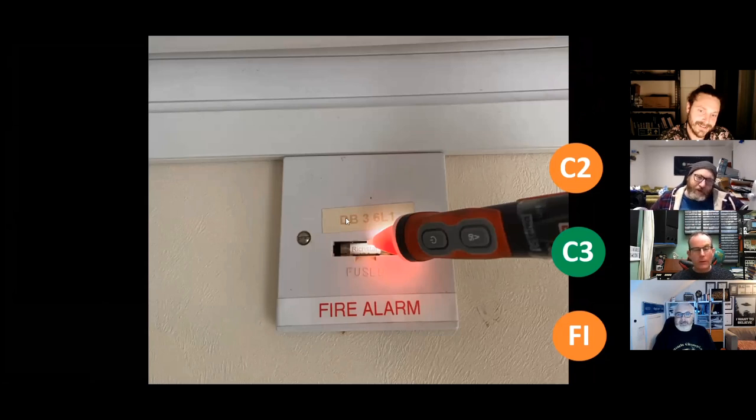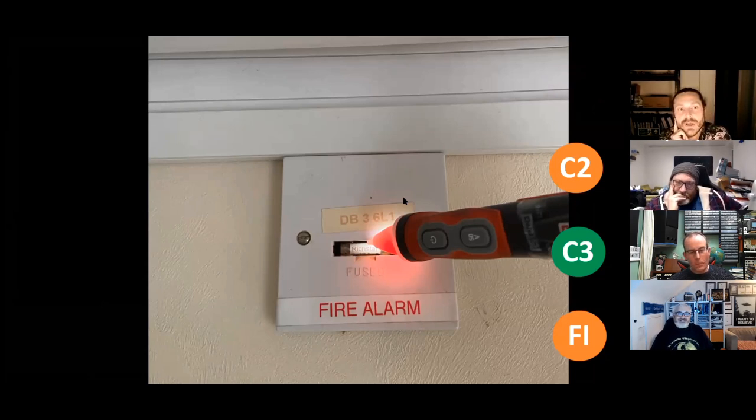What's that? Well, first of all, the label is just wrong. It's UV faded. Screws are horizontal, not vertical. That's wrong. See, I find this an interesting one because a lot of fire alarm technicians, engineers or operatives, whatever, a lot of them aren't too familiar with 7671. So I've become aware of this.